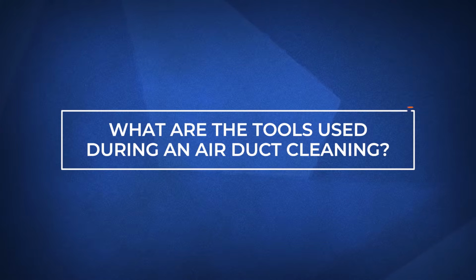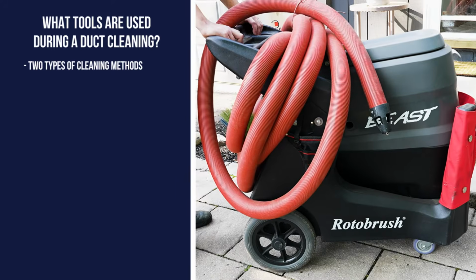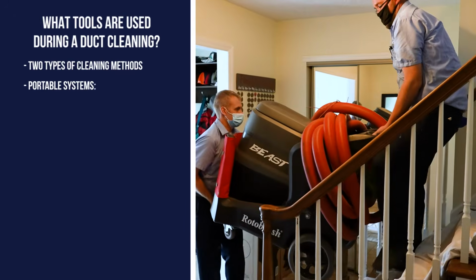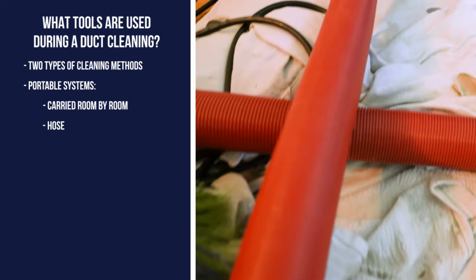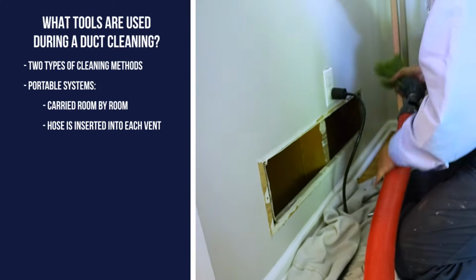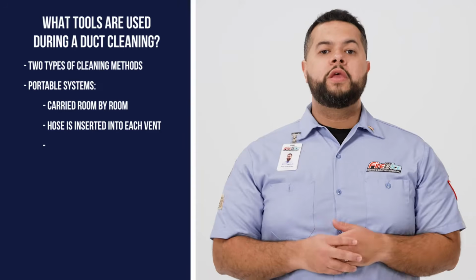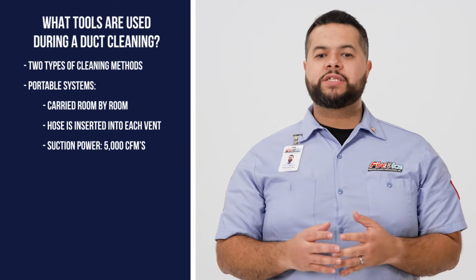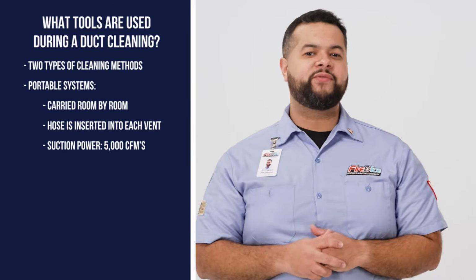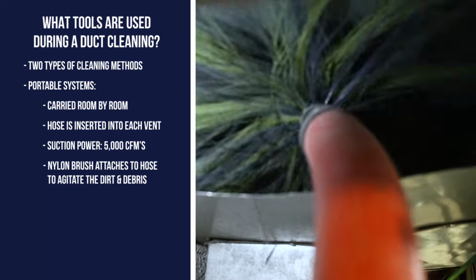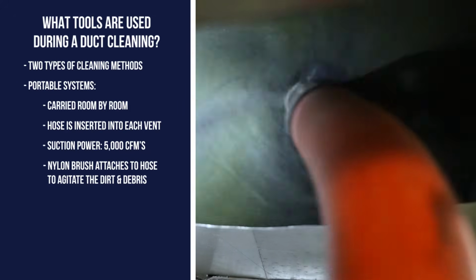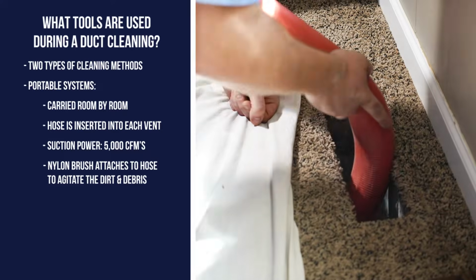What tools are used during a duct cleaning? The goal with every duct cleaning is to remove as much debris as possible from the ductwork. There are 2 vacuum types, portable and truck mounted. Portable systems are carried by technicians from room to room. A hose is then inserted in each room's vents to clean the ductwork. The largest portable vacuum has a suction power of about 5,000 cubic feet per minute. On the end of the hose is a nylon brush that spins, which scrapes away any dust and debris that's inside the duct. The vacuum then sucks any debris.